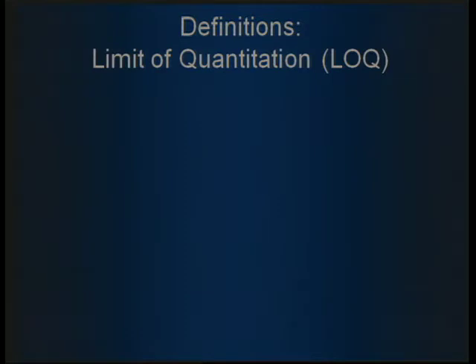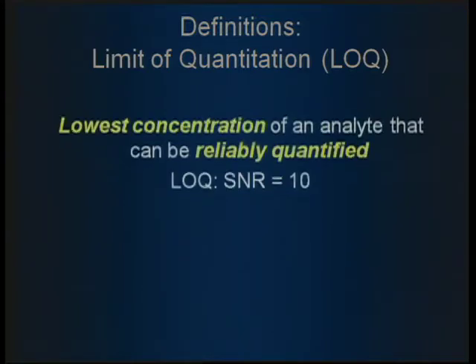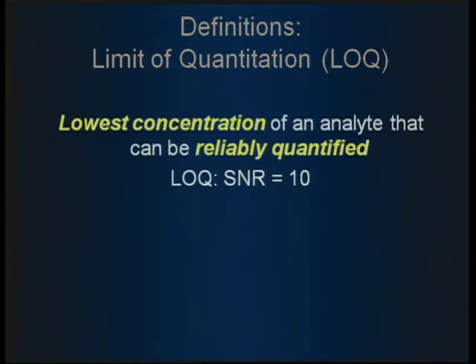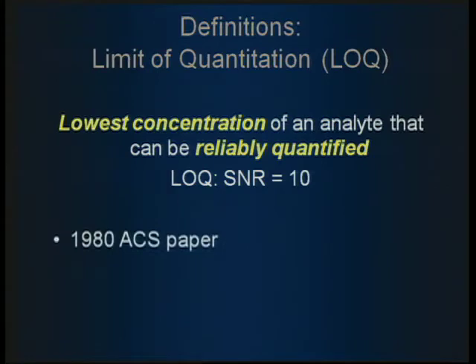The limit of quantitation, or LOQ: now you have a peak detected, but you want to be able to quantitate it. The LOQ is the lowest concentration of an analyte that can be reliably quantified. It corresponds to a signal-to-noise ratio of ten for a peak, from that same 1980 paper.